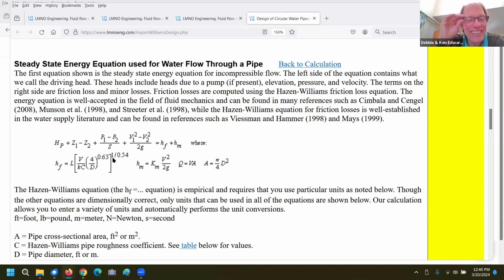So with one of these equations, you just hope the book's got the coefficients right. If it's not a form of an equation I'm super familiar with, I'll do a calc with the units and the equation I know work, and then use the equation in the book that uses different units and make sure the head loss comes out the same. It's an empirical equation. That's why you have these goofy looking coefficients like the 0.63 power and 1 over the 0.54 power. You could just punch that out on your calculator and get roughly 2 or something like that. But this equation had 1 over 0.54, so that's what I used. These coefficients were determined 100 years ago or more by Hazen and Williams. But it's the most widely used equation for municipal water distribution, even now, at least in the U.S.